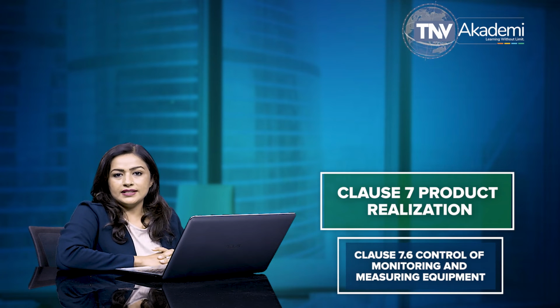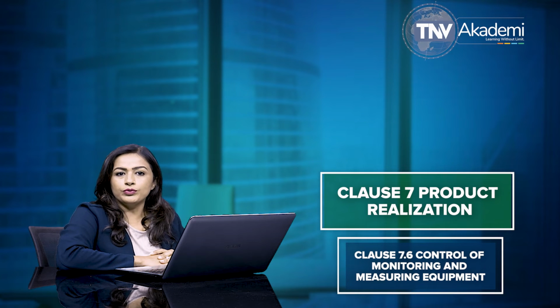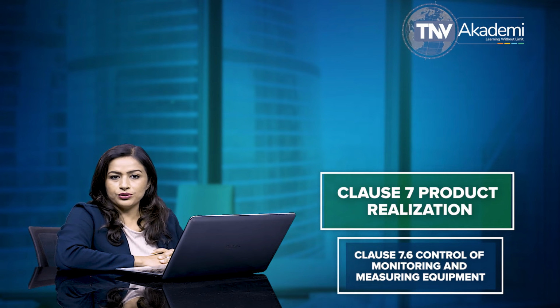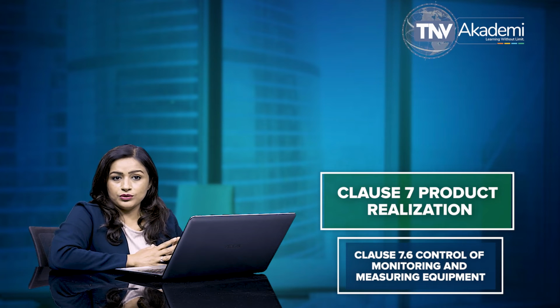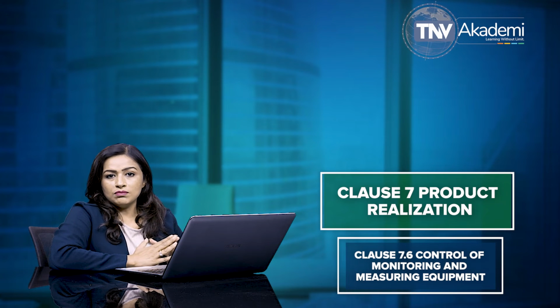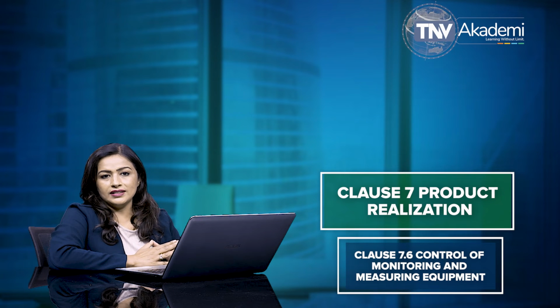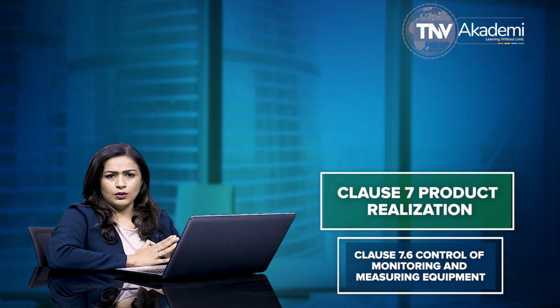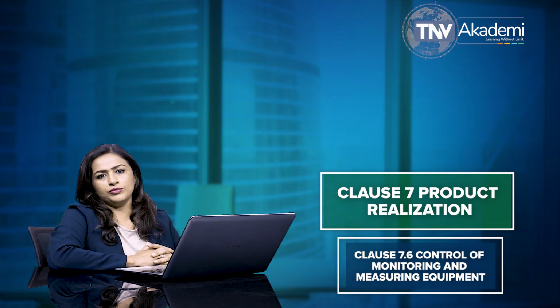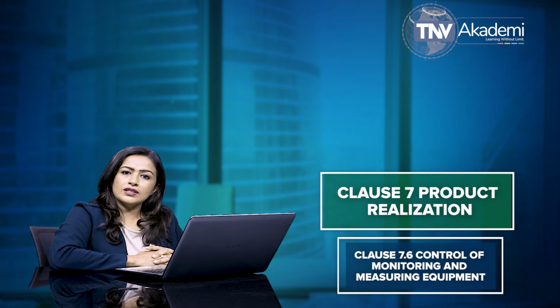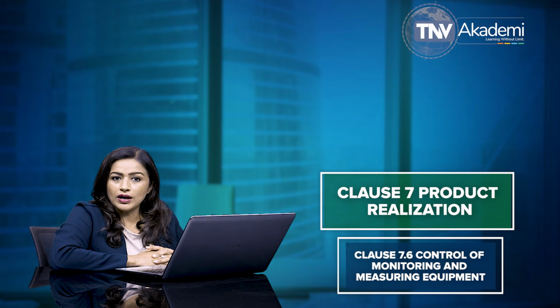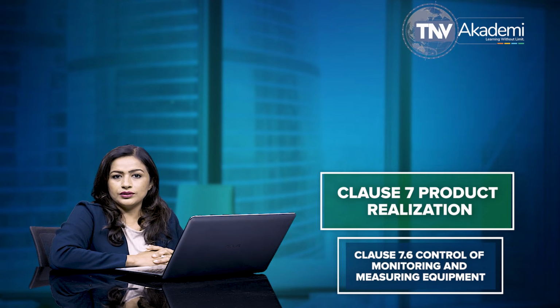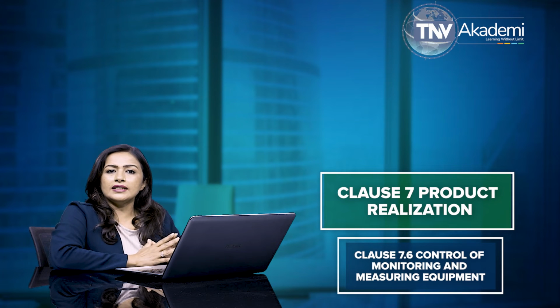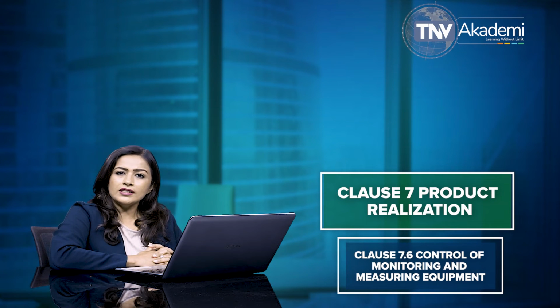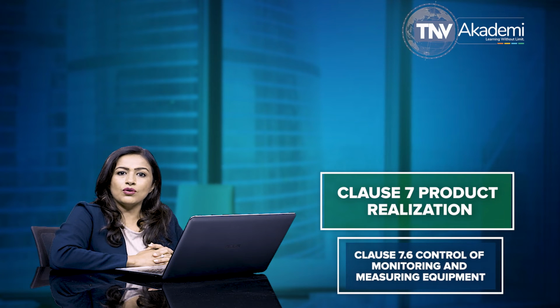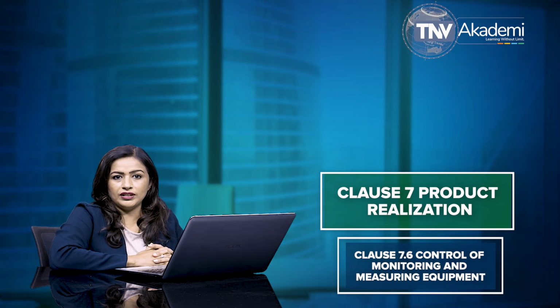Subclause 7.6 states that the organization is required to perform calibration or verification in accordance with documented procedures. In addition, the organization must assess and record the validity of the previous measuring results when the equipment is found not to conform to requirements. As per this clause 7.6, the organization is required to take appropriate action in regard to the equipment and any product affected. The organization is also required to maintain the records of the results of calibration and verification.